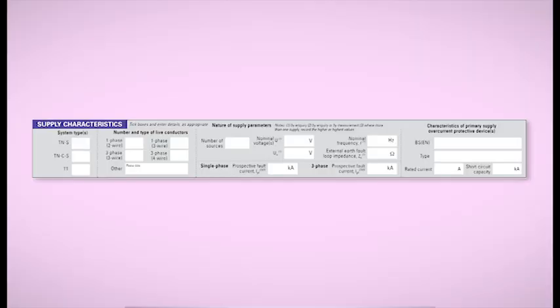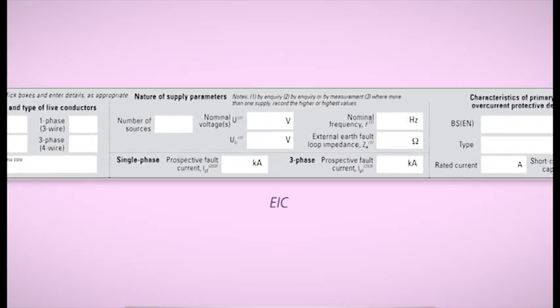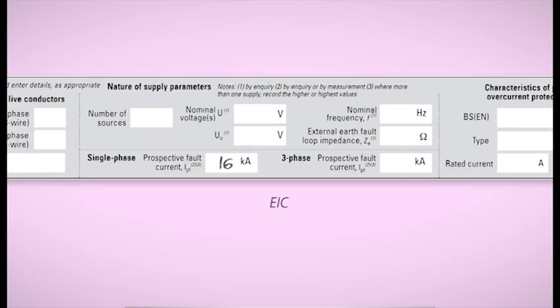The forms do allow us to either determine this by inquiry or measurement. However, I would normally expect the boxes under supply characteristics to be filled in with the data from the design information. This, on most occasions, will be values determined by inquiry. Typical values are 16 kA for single-phase supplies and 25 kA for three-phase supplies.